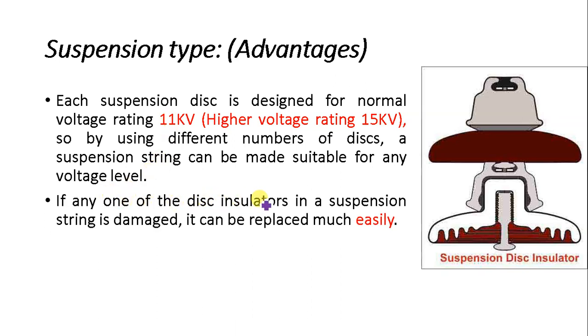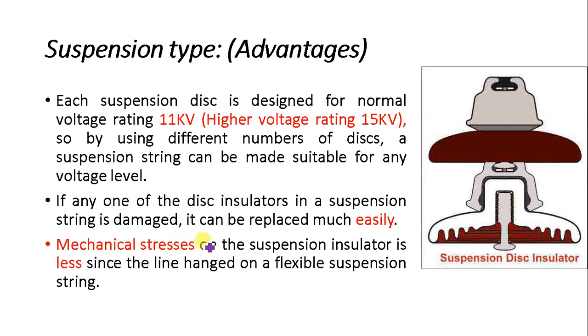Another advantage is that if any disc in a suspension string is damaged it can be replaced easily. For example, in a 33 kV system where three discs are typically used, if one disc is punctured due to a flashover, only that one disc needs to be replaced rather than the whole insulator string. Replacement is therefore much simpler and more economical.